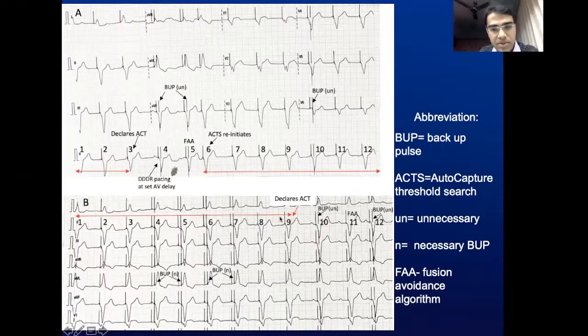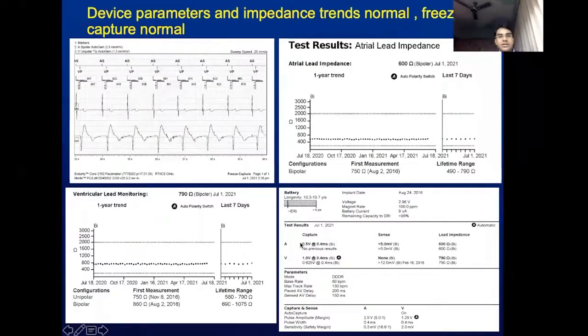During this auto capture threshold search, in this 9th beat, there was a declaration that this, whatever it may be, is the threshold. After that, with the addition of 0.25 volt, the device starts normal pacemaker functioning at a set AV delay. Unfortunately, in the very first beat, although there is adequate myocardial capture, for the pacemaker there was a loss of capture and an unnecessary backup pulse came in, and this kept on going. When we checked the device parameters, by that time the ECG had already become normal, and all parameters were normal, along with the freeze capture, which is also normal. The threshold and impedance trend, everything was within normal limits. The auto capture threshold for this patient was 1 volt at 0.4 for the ventricular lead.